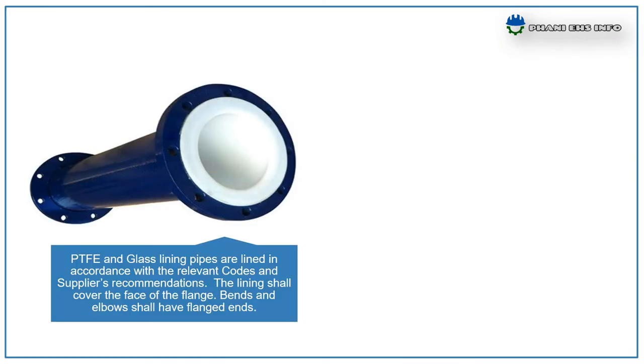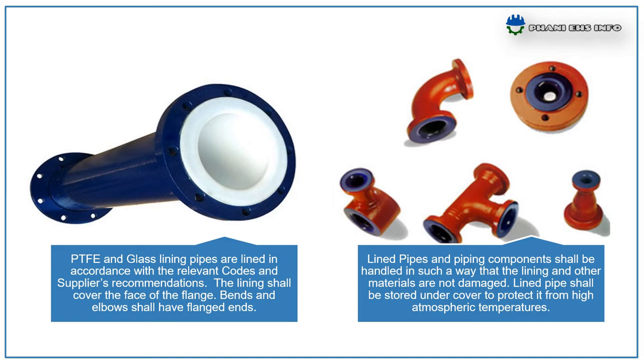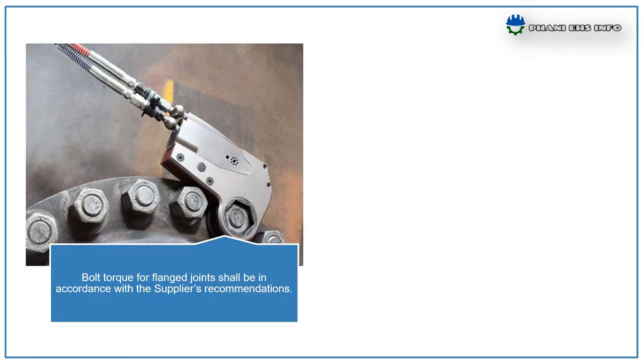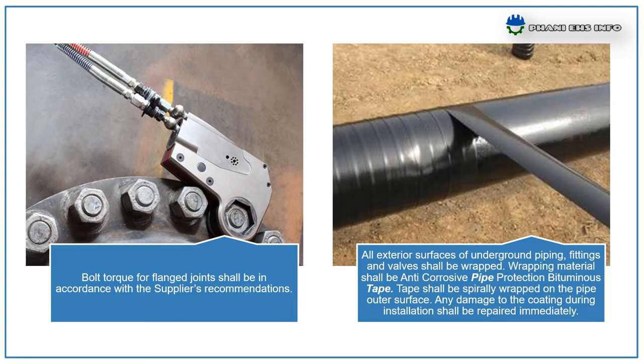PTFE and glass-lining pipes shall be lined in accordance with relevant codes and supplier's recommendations. The lining shall be flush with the face of the flange. Bends and elbows shall have flanged ends. Lined pipes and piping components shall be handled so that the lining and other materials are not damaged. Lined pipes shall be stored under cover to protect from high atmospheric temperatures. Bolt torque for flanged joints shall be in accordance with supplier's recommendations. All exterior surfaces of underground piping, fittings, and valves shall be wrapped with anti-corrosive pipe protection tape, spirally wrapped on the piping outer surface. Any damage to the coating during installation shall be repaired immediately.